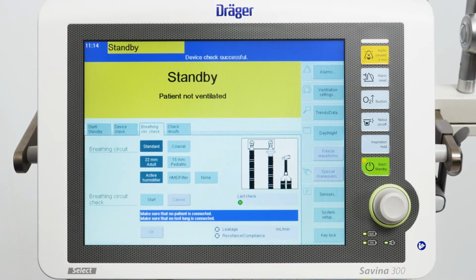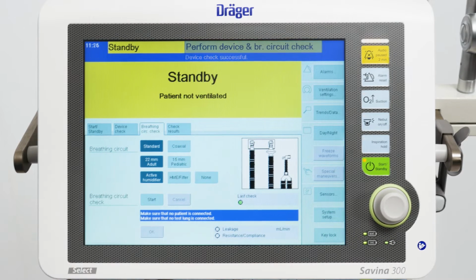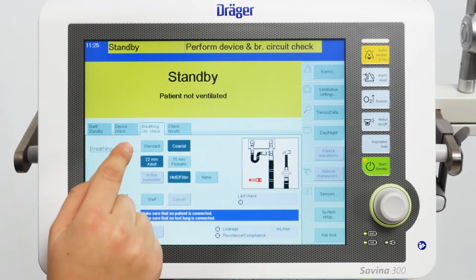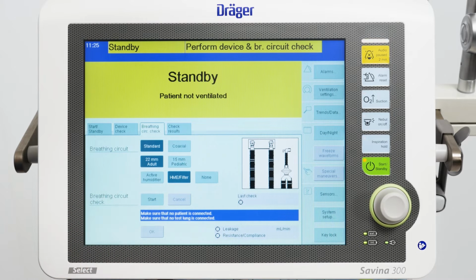After the device check was successful, perform a breathing circuit check. You already selected the breathing circuit check. Select the breathing circuit used, either standard or coaxial. Subsequently, select the corresponding button for patient type and the humidification type.